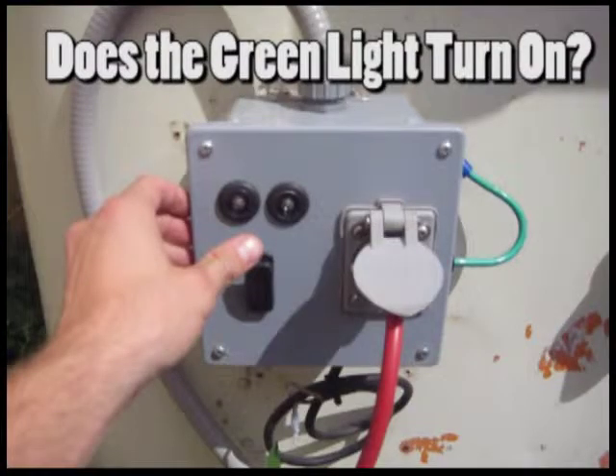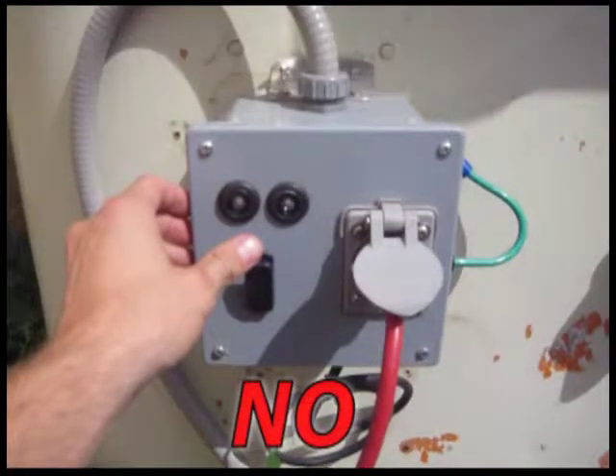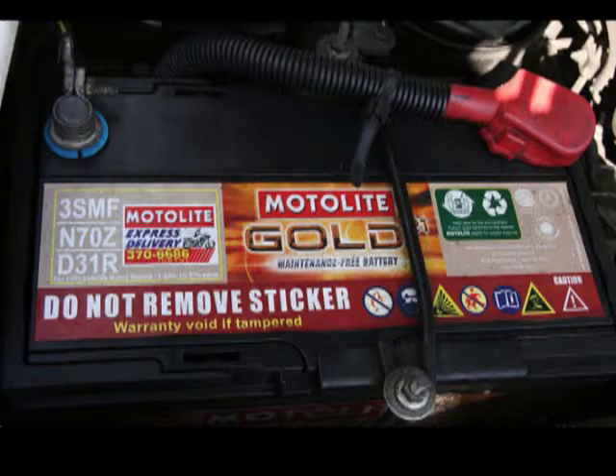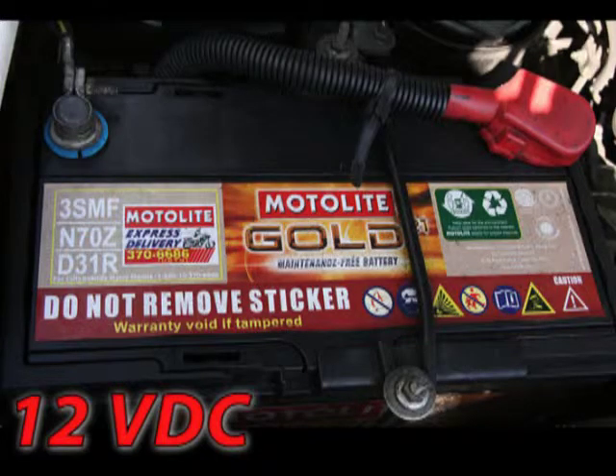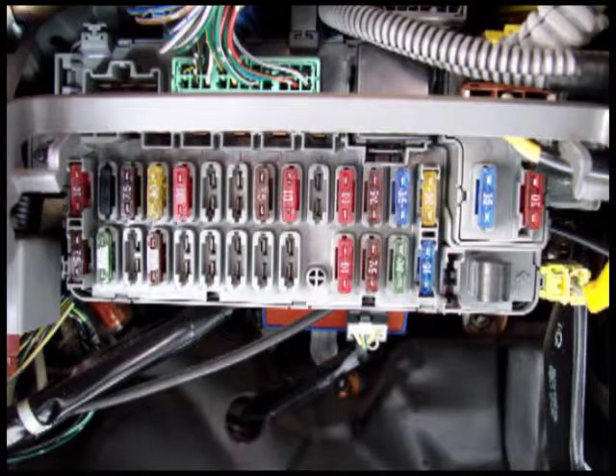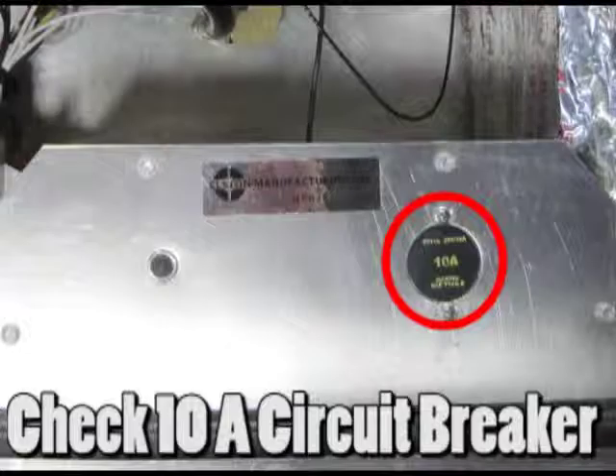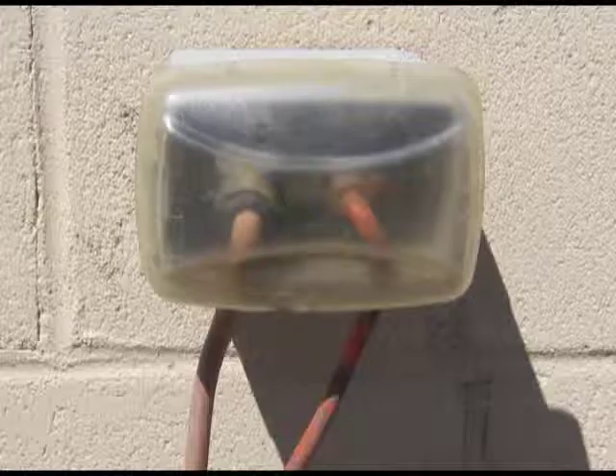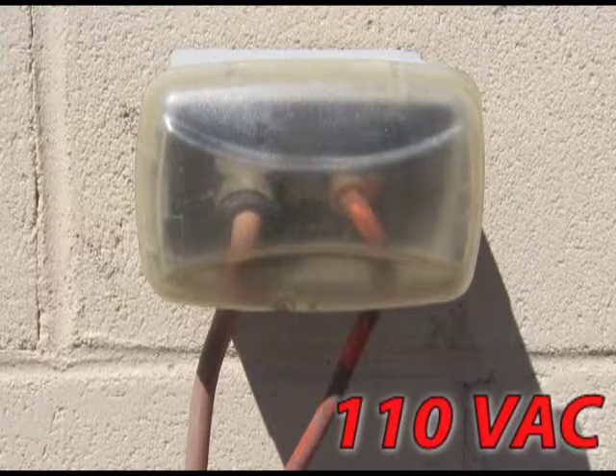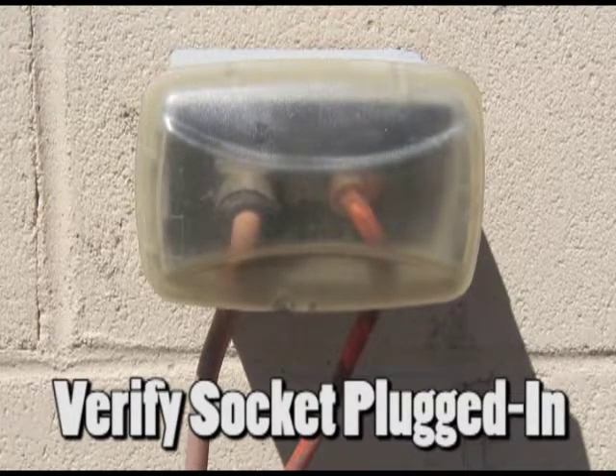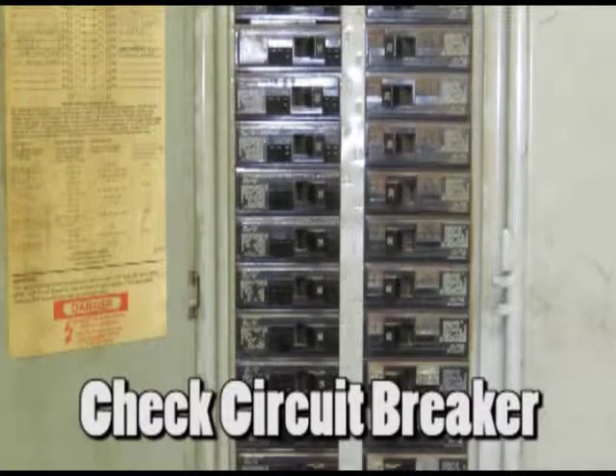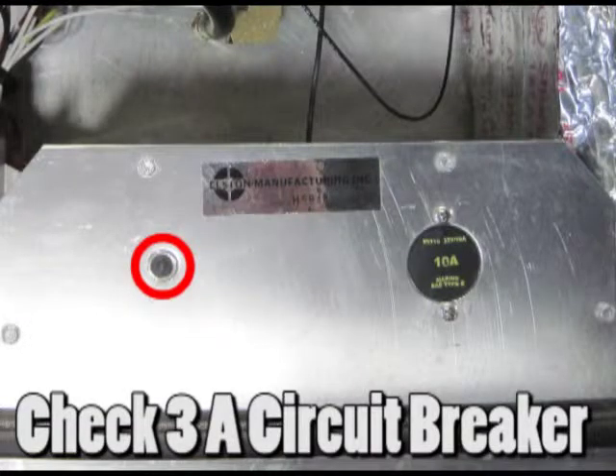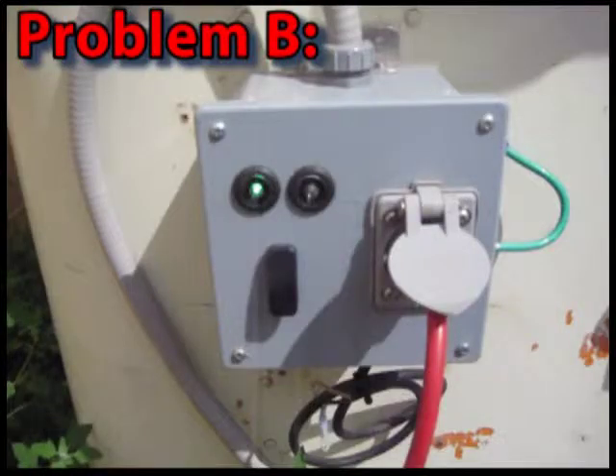If the green indicator light on the control box did not turn on, check to see if the heater is running off of trailer power. If so, check the fuse and the line supplying power to the trailer and the 10 amp circuit breaker on the electrical cover. If the heater is running off of 110 VAC, check that the extension cord is properly plugged in. Check the fuse and the circuit supplying power to the 110 VAC and the 3 amp circuit breaker on the electrical cover.